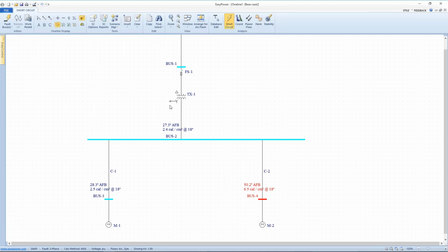He says, well, up here where I'm working essentially on the transformer, the arc flash boundary is 27.3 inches. The incident energy is 2.4 calories per square centimeter at a working distance of 18 inches. So I know what PPE I need to wear as I work on this bus. If I walk down to this bus, the arc flash boundary is 28.3 inches. Incident energy is 2.5, 18-inch working distance, I know what PPE I need to work on here.